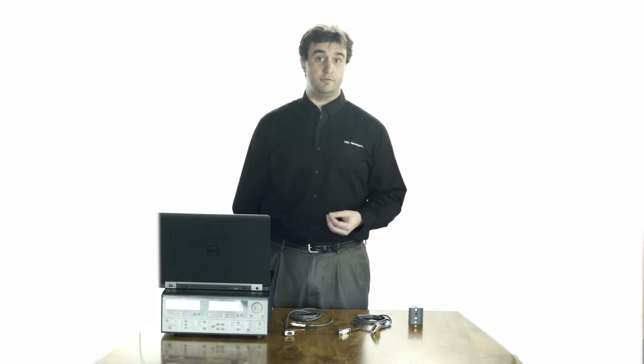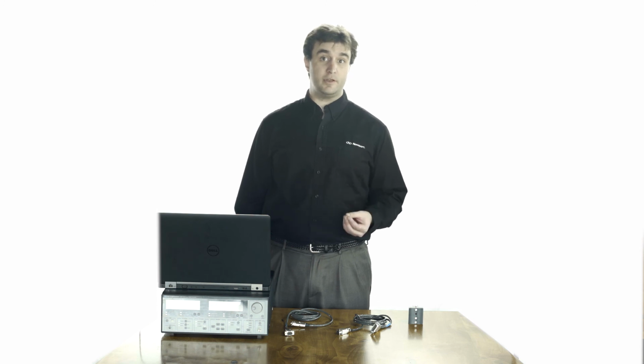LIV curves are essential to the characterization of laser diodes and represent the relationship between light intensity, current, and voltage. LIV measurements involve the use of a photodiode to measure the light intensity and equipment to measure the drive current and voltage that is supplied to the laser diode.